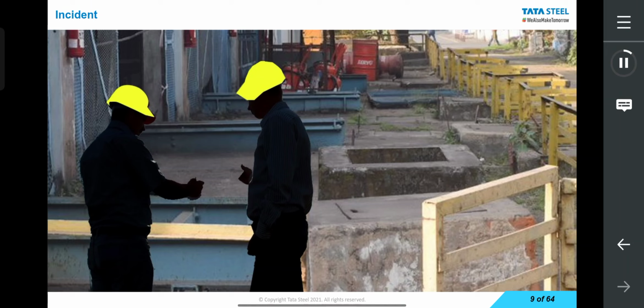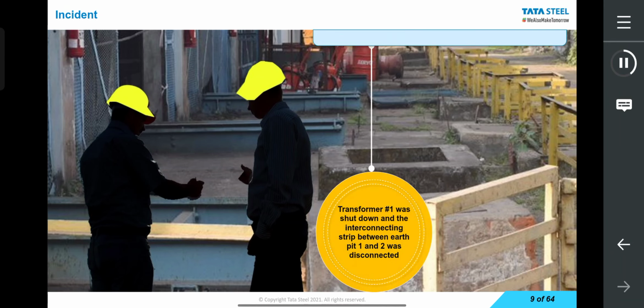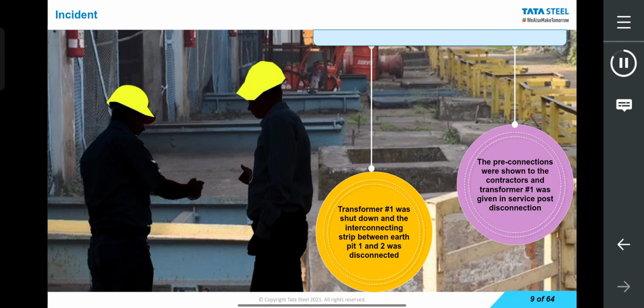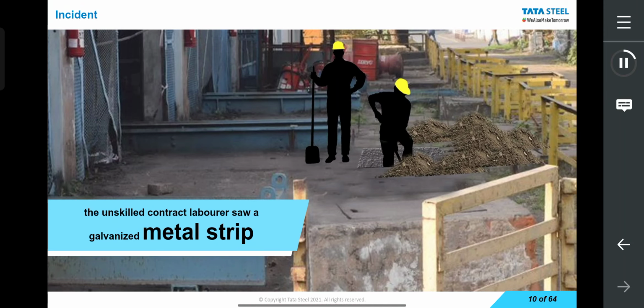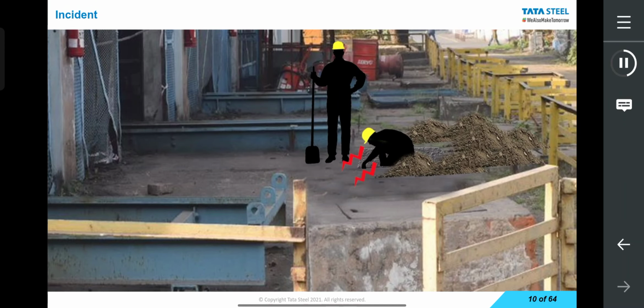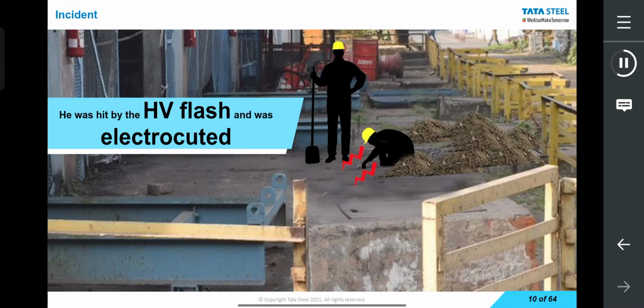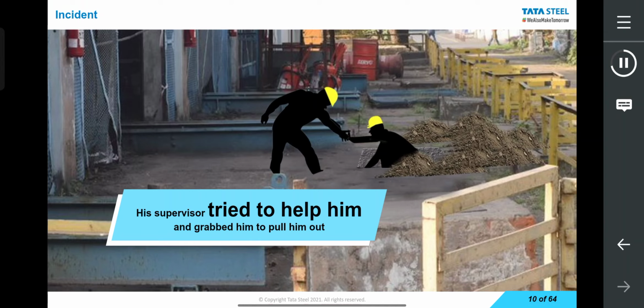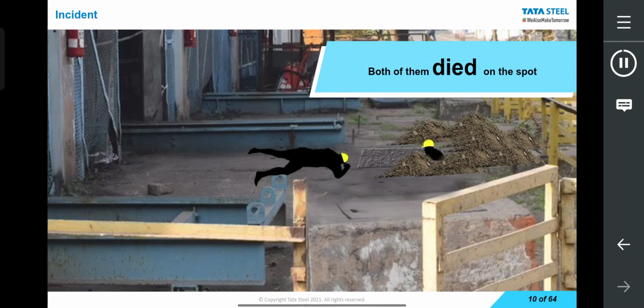On the execution day, 2 contractors, an unskilled laborer and his supervisor were involved in the job. As planned, transformer 1 was shut down and the interconnecting strip between earth pit 1 and 2 was disconnected. The pre-connections were shown to the contractors and transformer 1 was given in service post-disconnection. It was a sunny day. After hours of digging, the unskilled contractor laborer saw a galvanized metal strip beneath the ground. Ignorantly, he touched the strip to remove it. He was hit by the HV flash and was electrocuted. His supervisor tried to help him and grabbed him to pull him out. He too was electrocuted. Both of them died on the spot.